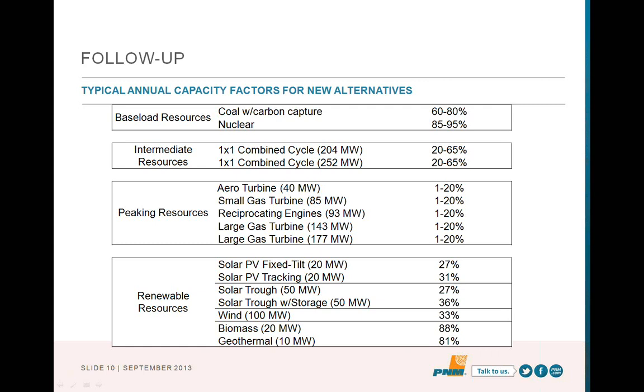We're kind of caught on that between what we know, because the two wind farms that we're looking at, the one that we are currently using, the New Mexico Wind Energy Center, and the one that we're proposing to buy, the Red Mesa, both of those have capacity factors that are a lot less than 33%. So then when we get presented bids for future wind centers and the bids have capacity factors that are higher, we don't have any way to verify that if it's not an existing facility.